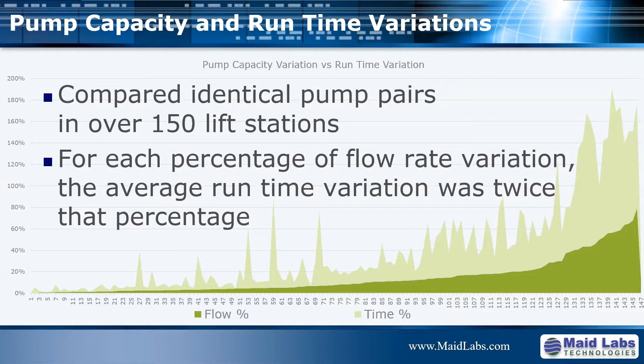And this is true at 1%, it's true at 5%, and it's true at 20%. So if you can gain 1% of pump capacity, you will reduce the runtime by 2%. This is a major thing. So you can use that as a rule of thumb on how it can be used. You will see right away, right now. So let's see how a standard lift station works.